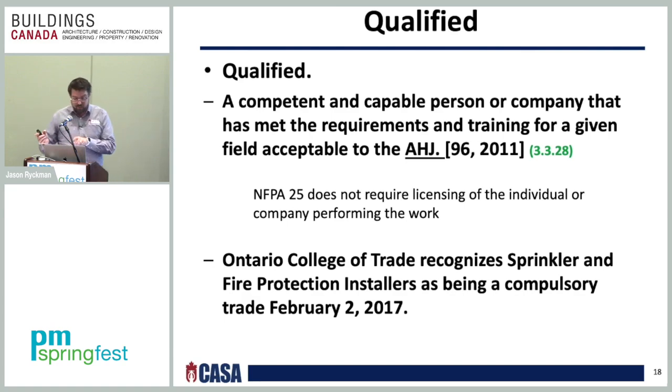The company has to meet the requirements and training for a given field acceptable to the authority having jurisdiction. So NFPA 25 does not require licensing of individuals or companies. It leaves it up to the authority having jurisdiction, or in our case, the province.